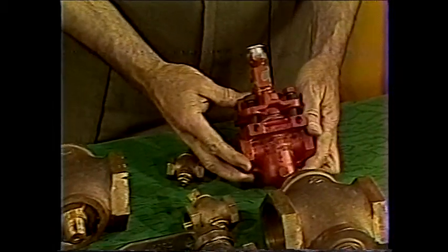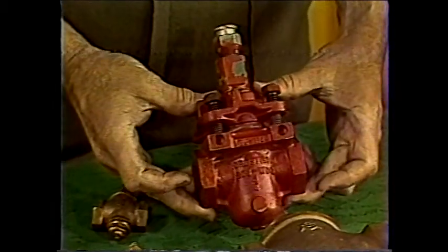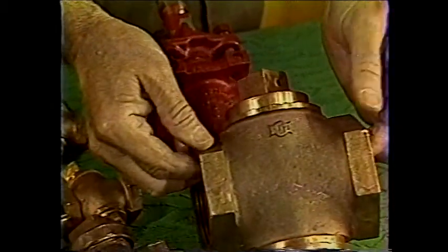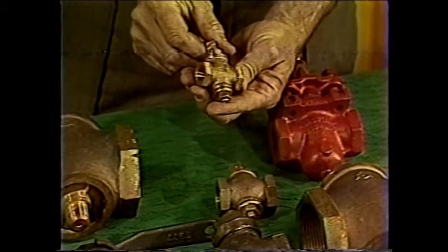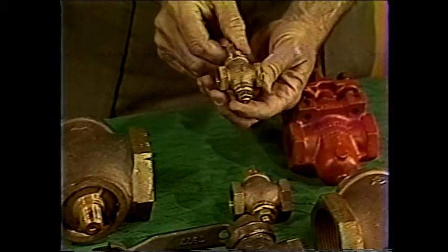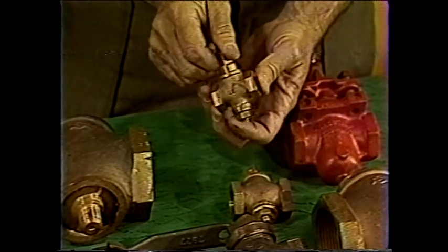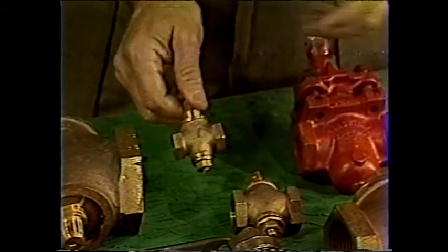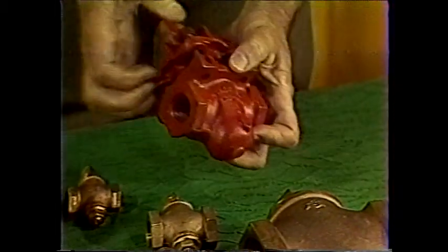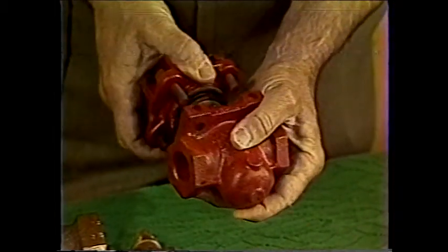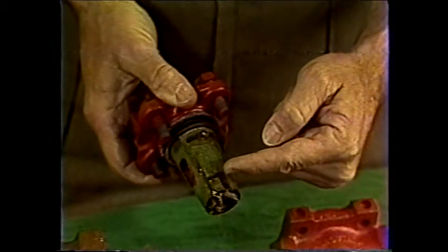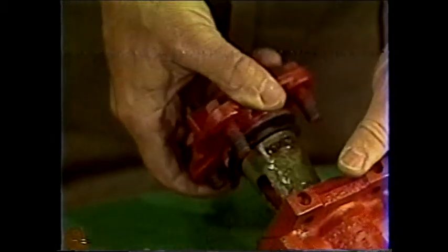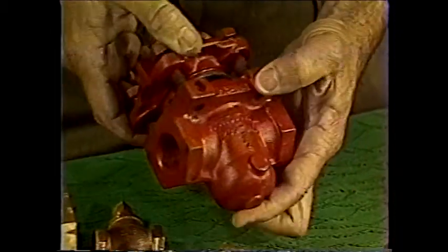Common plug valves come in 2 styles. The lubricated like this, and non-lubricated like this. The non-lubricated plugs, especially in the smaller sizes, are also called plug cocks. For example, a steam cock is just a small, non-lubricated plug valve used for steam. Lubricated plug valves use some type of material like heavy grease or plastic, which is not affected by the material being handled by the valve. This lubricant is forced under high pressure through grooves like these. This pressure tends to lift the plug off its seat and make it easier to operate.